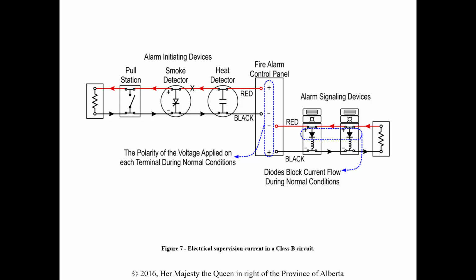Pretty straightforward. Then it starts talking about, in objective 3, field devices. And this is kind of how we're going to start wiring our fire alarms together. So a field device is a remote device in a fire alarm system that is electrically connected to a control unit. We have initiating, signaling, and supervisory. So initiating, basically it's just going to say is it normal or is there a fire condition? So that'd be your smoke detectors, heat detectors, pull stations, that kind of thing.